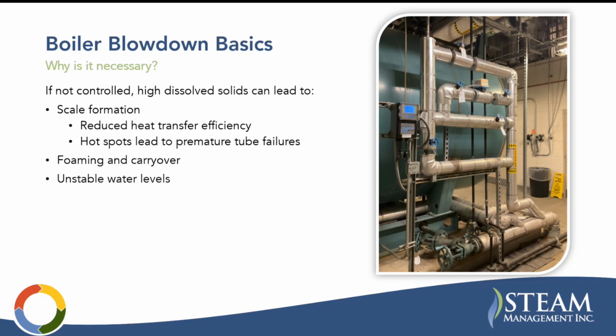Another thing it can do is foul up your level control equipment, which can lead to a dangerous scenario. That's one of the most important safety devices in the boiler. The scale can build up in there, but also the foam in the water can lead to false readings in your level controls. So it is absolutely necessary, but it is inherently wasteful.